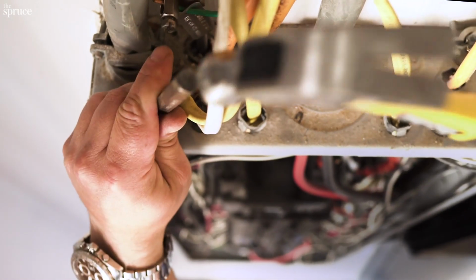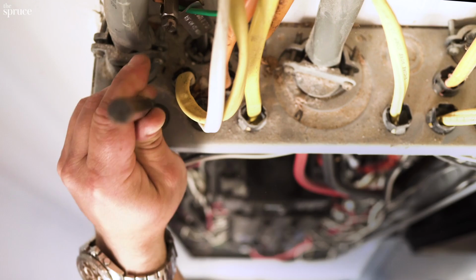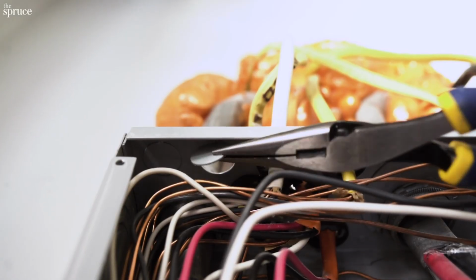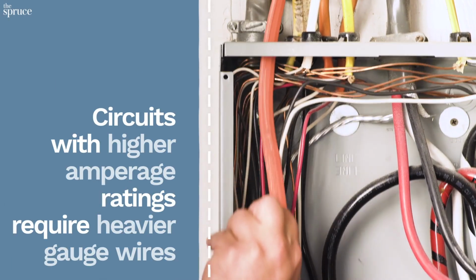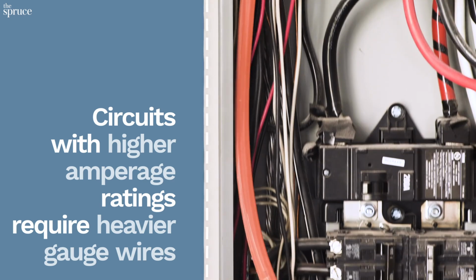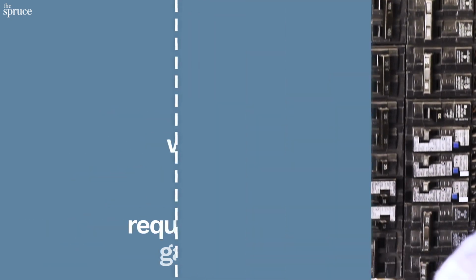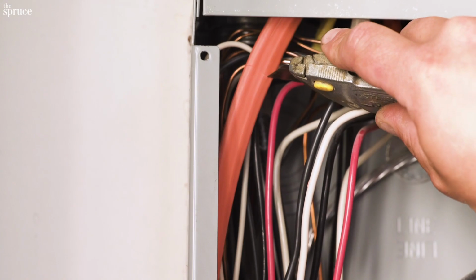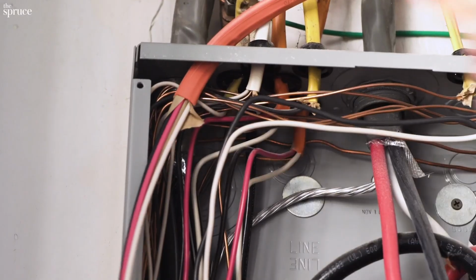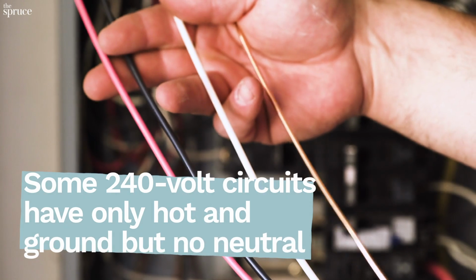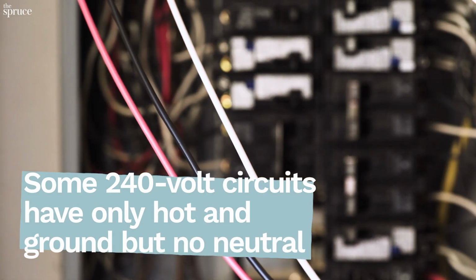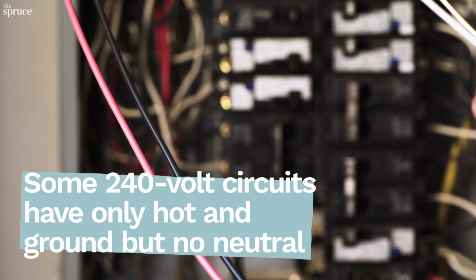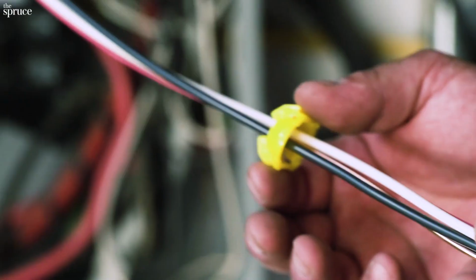Now we'll prep our circuit wires. Remove a knockout on your box so you can feed in your new circuit cable. We're using cable with 10 gauge wire, which is standard for a 30 amp circuit. Okay, slice open the cable jacket with a utility knife to expose the individual wires. Be careful here not to cut the insulation on any of the wires. Here you see the bare copper wire, that's our ground. The white wire is our neutral, and the red and black, those are our hot wires.